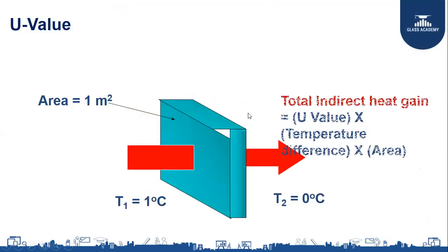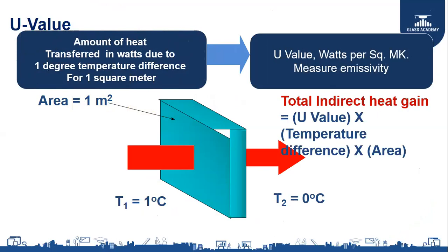Next is the U value. So today, assume that outside the temperature is 35 degrees. The summer has already started. It can range between 35 and 40 degrees here in Chennai. And inside, if you are in an AC room, you will usually keep the temperature at 24 to 26 degrees, approximately 25, let us assume. So 35 minus 25 is 10 degrees difference in temperature. In this 10 degrees difference in temperature, heat moves from the outside to the inside. So how much is that amount of heat is the question. So how do you answer that?